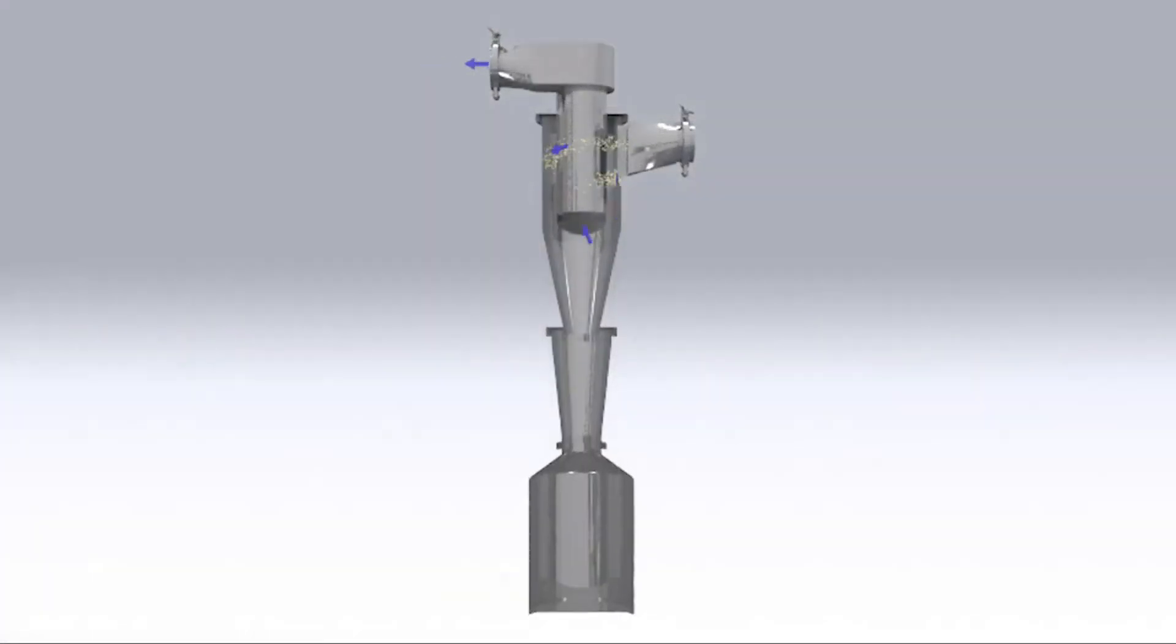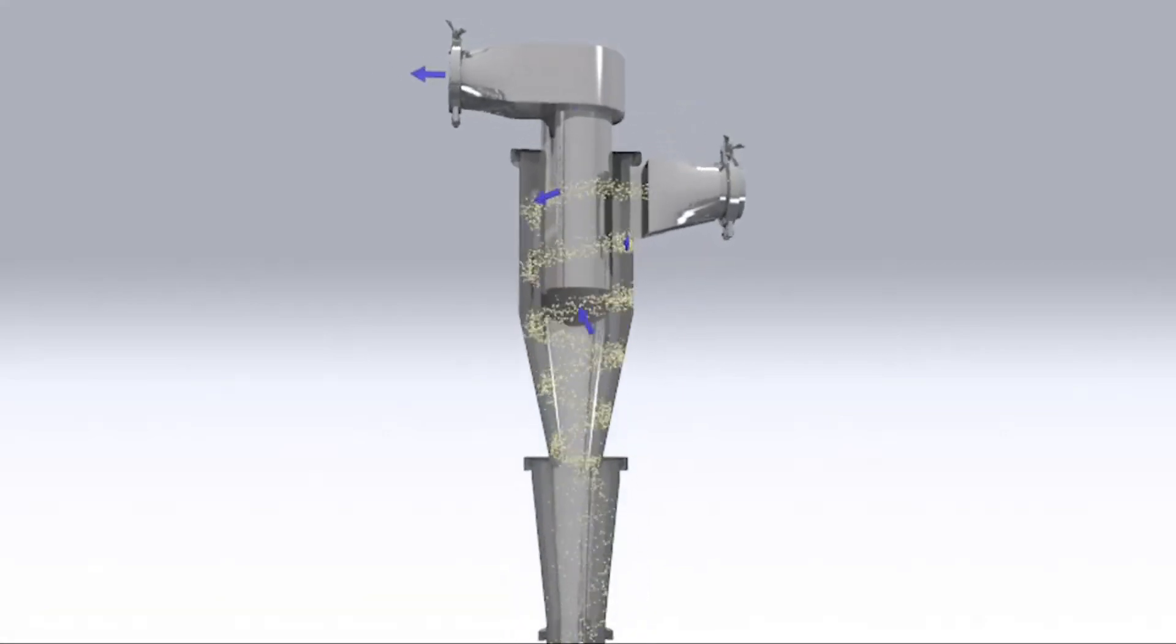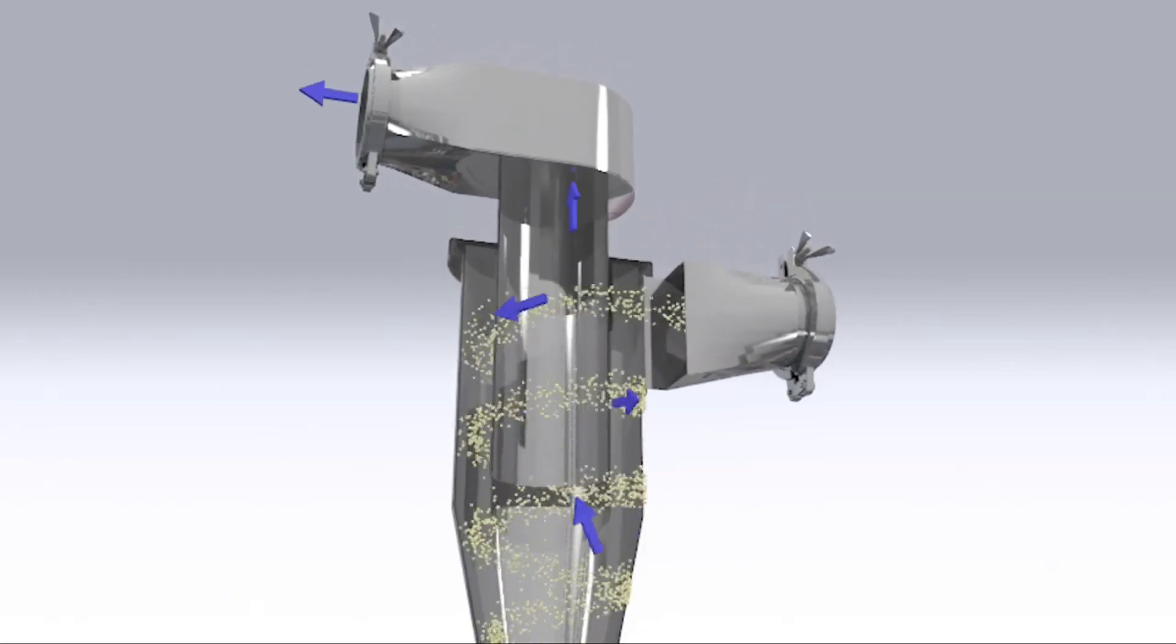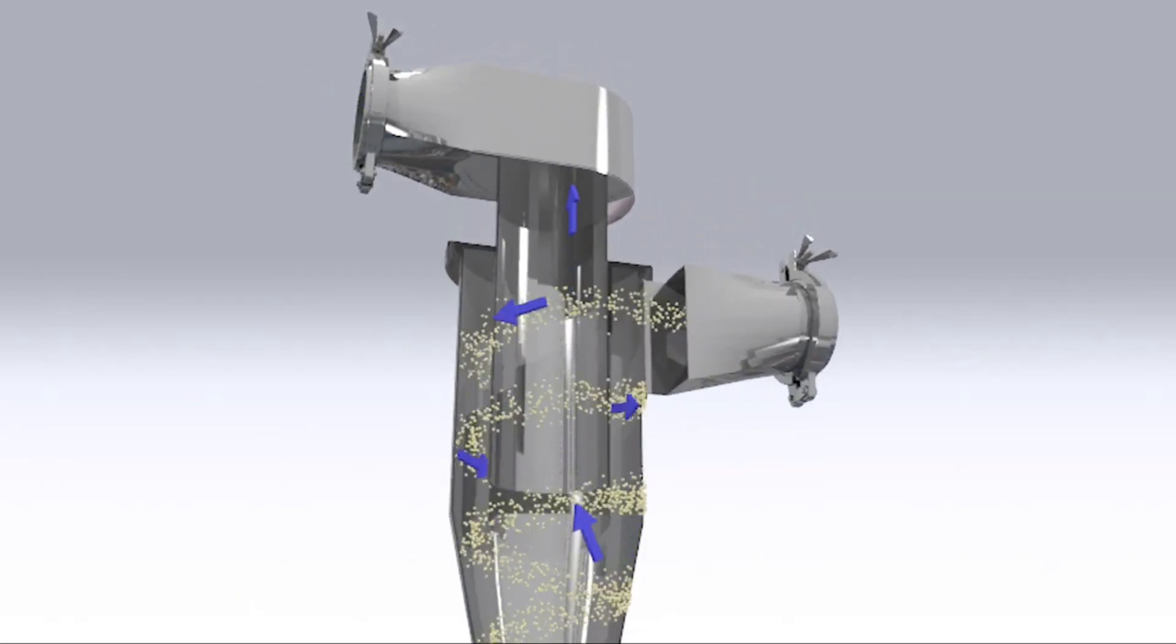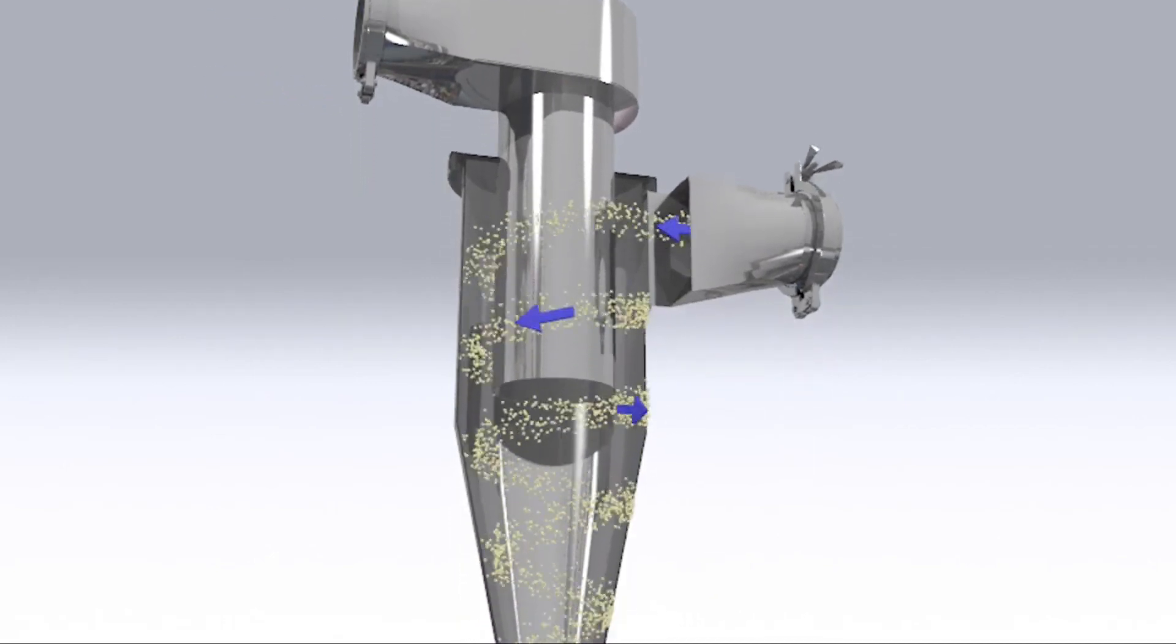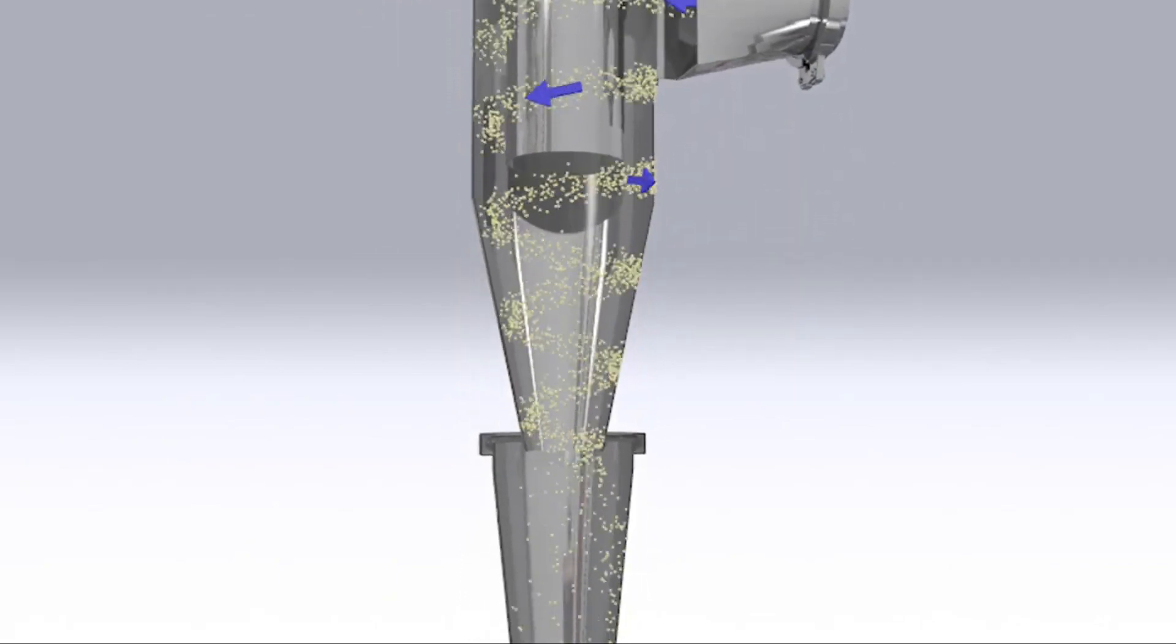Inside the cyclone, vortex separation causes the solid particles to hit the outside wall of the cyclone and fall to the catch pot, allowing clean air to pass downstream to the dust extraction source. The captured waste material can be used for batch loss reconciliation or even reintroduced to the process where protocol permits.